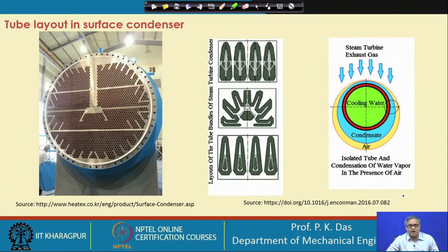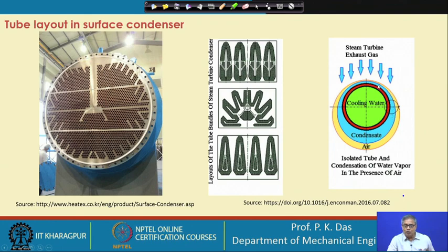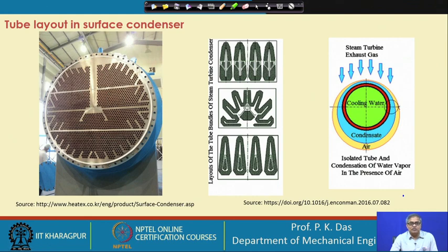When steam comes to the condenser for condensation, it will carry air along with it. Air is a non-condensable. Schematically, the cooling water is inside the tube, outside is the tube wall, then the condensate film, but outside that there will be a layer of air — a fairly dense collection of air — meaning no vapor molecules are nearby. After some time, condensation gets hindered, more air accumulates inside the condenser and its quantity keeps increasing.